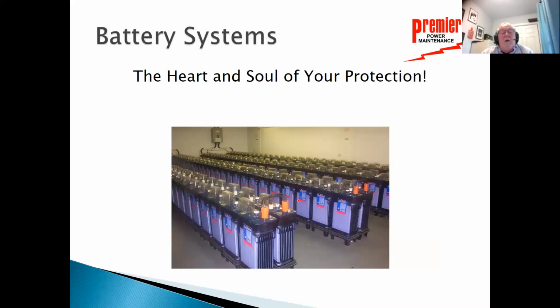I actually got called out one night to a large industrial facility where they had a battery that hadn't been maintained so long that actually one of the leads corroded off, and for an interim they just came in and they plugged in a battery charger and put the battery charger in the place of where that battery had been. It didn't last the entire night, and that was a real problem for them.